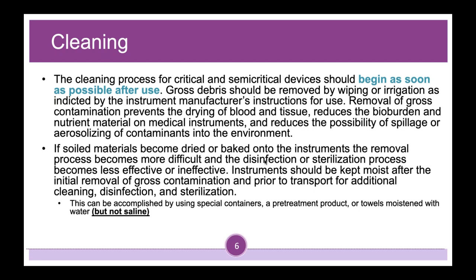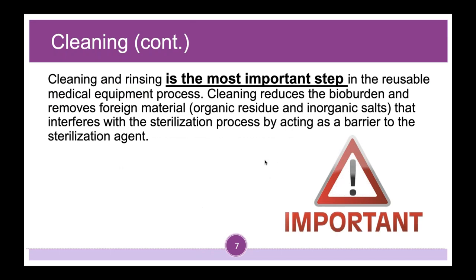This slide is extremely important. It's a very important aspect of infection prevention. Cleaning and rinsing is the most important step in the reusable medical equipment process. Cleaning reduces the bioburden and removes foreign material, organic residue, and inorganic salts that interfere with the sterilization process by acting as a barrier to the sterilization agent.